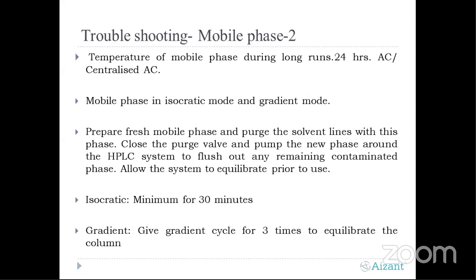As per practical experience, even for isocratic mode, depending on the choice of mobile phase, we should equilibrate the column for a minimum of 30 minutes. If you are using a gradient system, kindly equilibrate the gradient cycle at least 3 times before starting your sample analysis or standard injections. If you are not equilibrating for 3 cycles, the drift in the baseline of the gradient will reduce with each injection. So the suggestion is to always have a 3 cycle equilibration before injecting a standard. Then you will pass your system suitability and there won't be any RSD challenges.